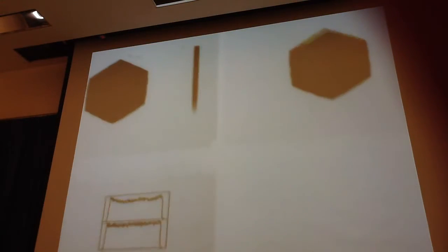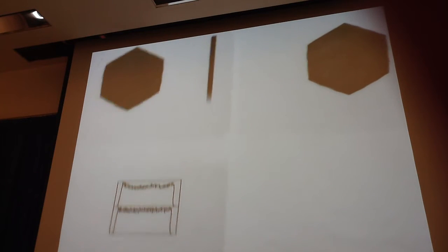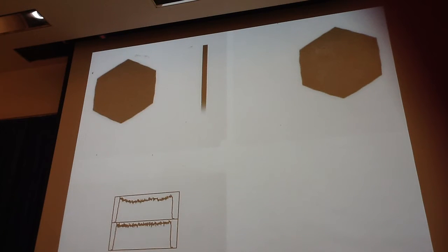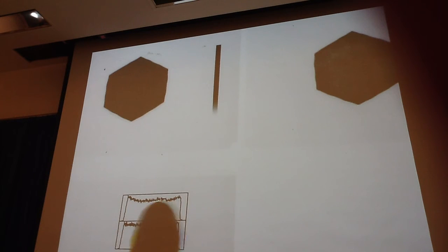Okay, here's another example of that. It's basically a uniformity test where they're just creating a profile. You can see the difference on here. Here's the uncorrected and here's the corrected. So there's the uncorrected over here and here's the corrected over here. You see the difference? The Gamma camera has noticed the areas that need to be changed.